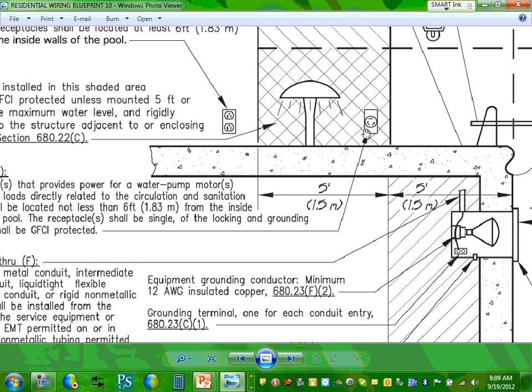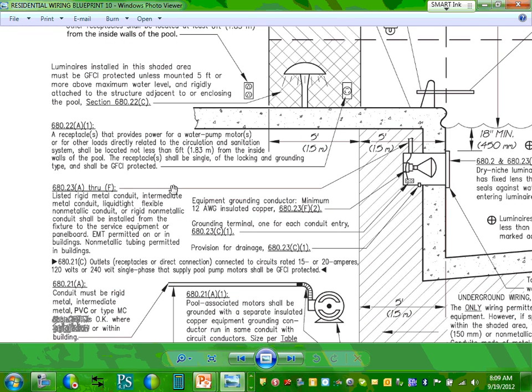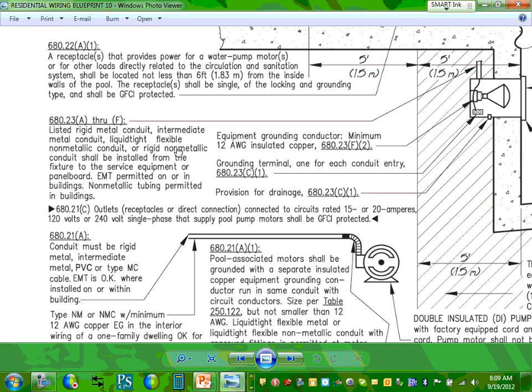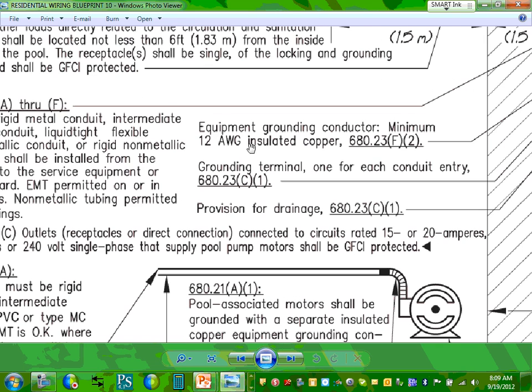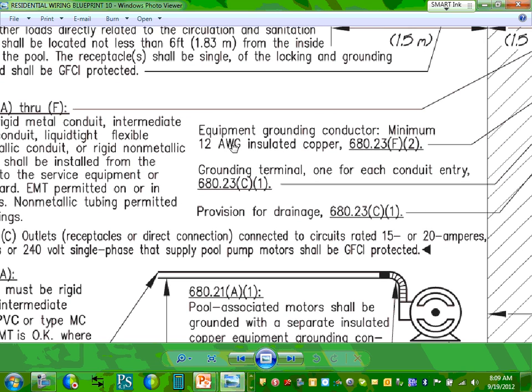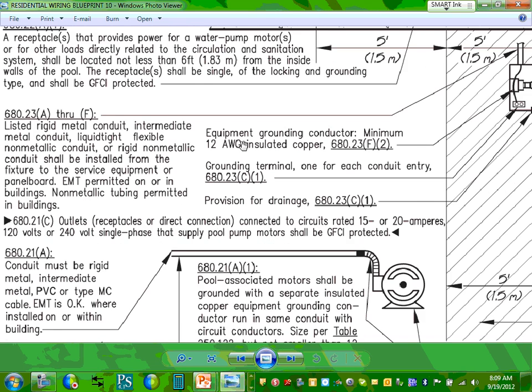It can't be closer than 6 feet. That's 6 feet for the receptacle, and it has to be GFCI. If it's 120 or 240, 15 and 20 amps, it has to be GFCI. So there's a lot of stuff, guys, about this one. Moving into this area, you can see the equipment grounding conductor is number 12 minimum for the wet niche and luminaires that we talked about.